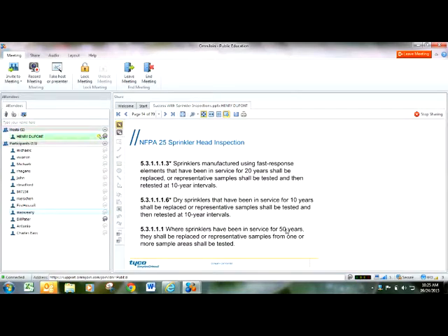So while you're on your inspections, you might just walk over to the sprinkler riser, and every sprinkler riser is supposed to have a spare sprinkler head box there with sprinkler heads in it that were from the initial installation. You can pull one of those sprinkler heads out of the box, and every sprinkler head is stamped with a date on it. If you've got quick response sprinkler heads that are over 20 years old, it needs to be written up that they need to be replaced or tested. 10 years for the dry heads and then 50 years for the standard heads. Again, that's a pretty easy inspection, low-hanging fruit there.